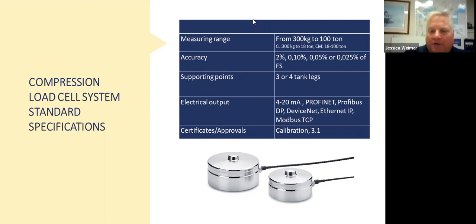Again, go back to the accuracy here. So you've got weight or accuracy ranges you can pick from, and these are also very common to what you would see for accuracy ranges with a strain gauge. However, there's a couple of things to think about. There's a difference between accuracy and resolution. And our load cells are certified or can be certified as accurate as OIML level 6, which is a super high accuracy and is among like the highest accuracy strain gauge load cell you can get. We can match that. However, our resolution can be up to 3 times better than a strain gauge cell.